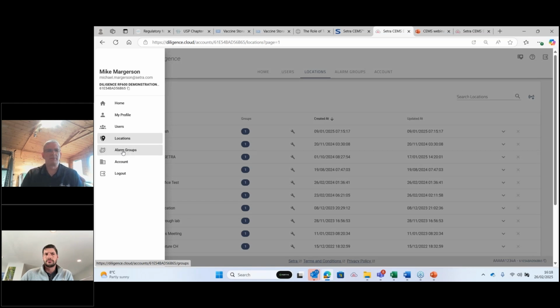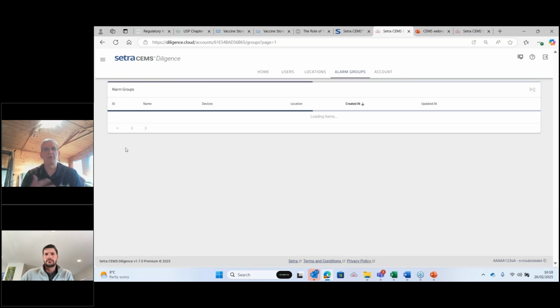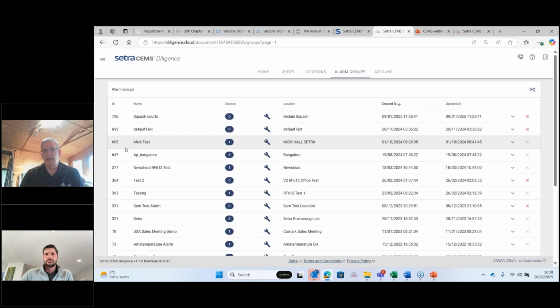Alarm groups are associated with that location. You can hit alarm groups and create a number of alarm groups for that location. For example, you might have a laboratory with 3 different sections, and you want to make 3 different alarm groups under that laboratory. There might be people with different responsibilities for each alarm group - one person responsible for alarm group 1, another for alarm group 2. You can associate their names, email addresses, and contact details, and only they will get notified of alarms within their particular location. So it's very flexible in how that works.